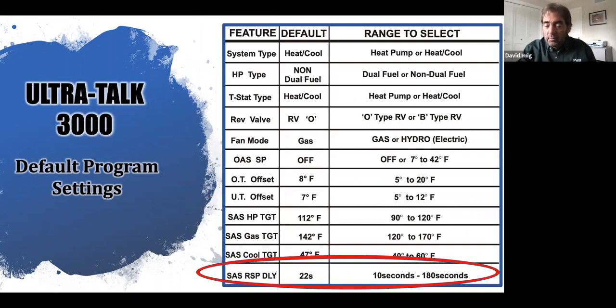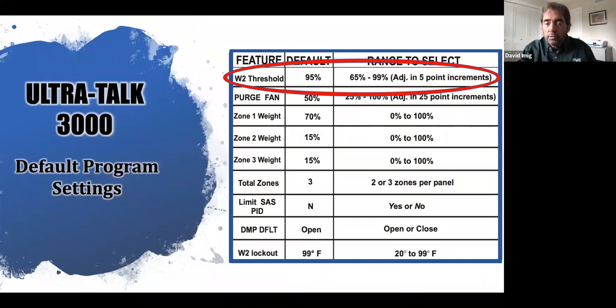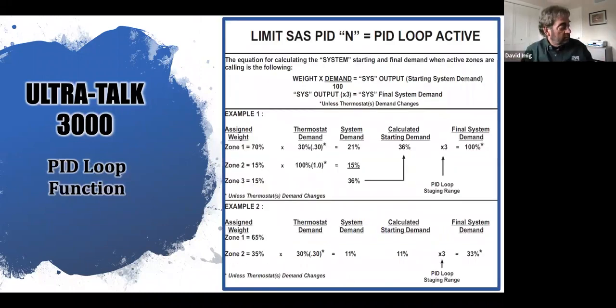Response delay is the time that we've selected, that in real time, how often is our supply air sensor looking at the temperature and feeding that information back to our panel. And then our threshold: when do we bring on auxiliary? So let's take a look at what our PID loop does. And this is when we're using our PID loop.